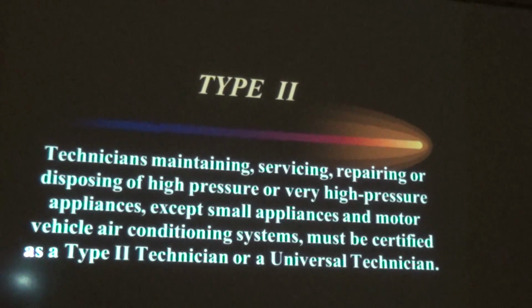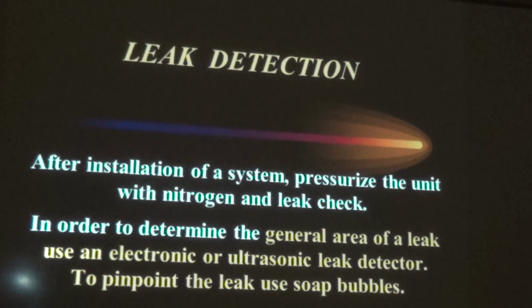Type 2: technicians maintaining, servicing, or repairing appliances that are considered high pressure or very high pressure, that have more than 5 pounds of refrigerant, have to be a Type 2 tech or hold Universal. Examples are split air conditioning systems and heat pumps. Leak detection: after installation of a system, you will pressurize the system with dry nitrogen and leak check. To determine the general area of a leak, use an electronic or ultrasonic leak detector. To pinpoint the exact location of that leak, use soap bubbles.